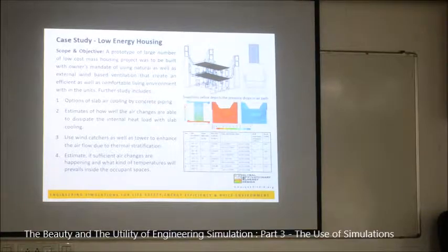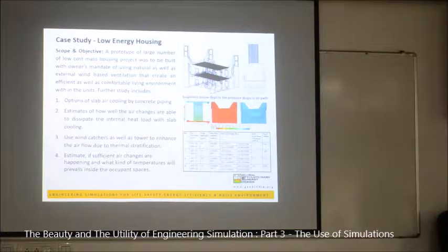One more aspect: let's say the slab is flat. Now, by incorporating these vents below that, will it affect the slab? No, it's not below, it's inside, sandwiched in the slab. You have a slab, and you have vent 1, 2, 3, 4. So it's actually saving on concrete also. They are not pouring concrete where the vents are. It's slightly thicker, but it has a channel of airflow inside it.